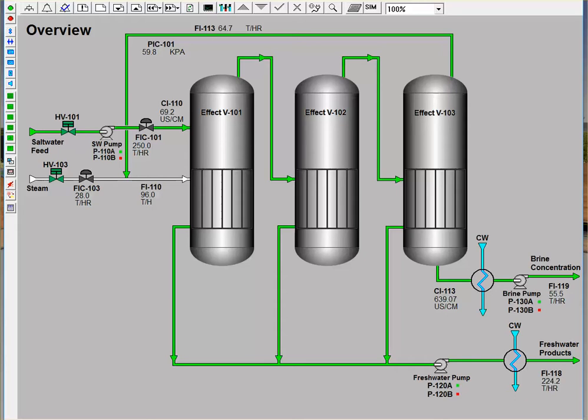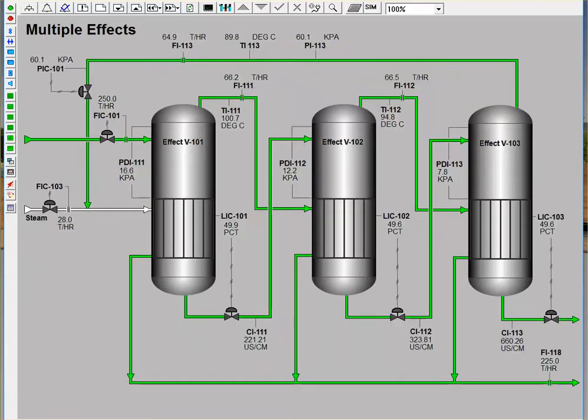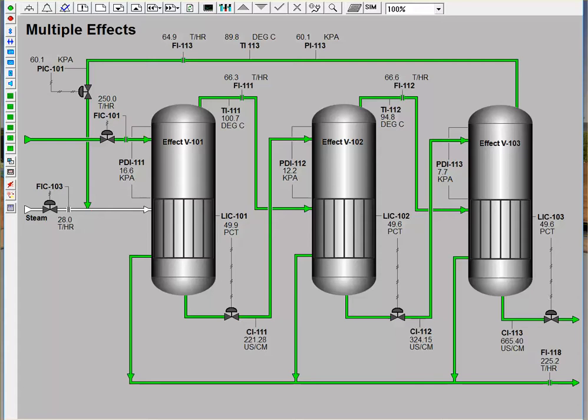Now we will move to the second schematic, and we'll see in more detail how different variables around each evaporator are maintained at their desired set points. We also will see the different flow, pressure, and temperature indicators, which can be seen by operators to ensure that the system is running properly. The salt water feed to the first evaporator is kept at approximately 250 tons per hour using a flow controller. The steam entering the first evaporator operates at nearly 28 tons per hour also using a flow controller. In addition, the pressure of the recycle stream is kept at about 60 kPa using a pressure controller.